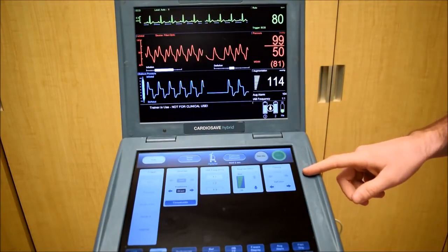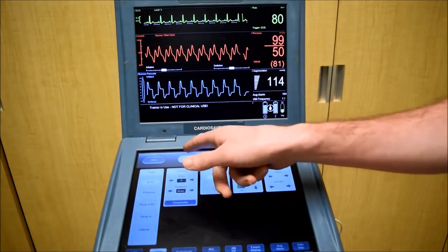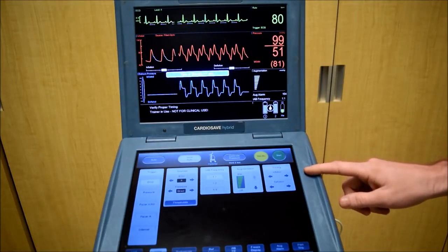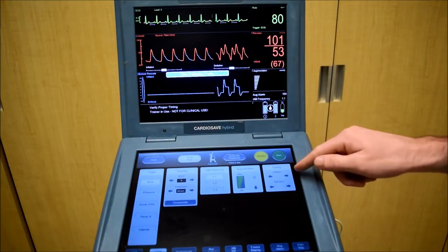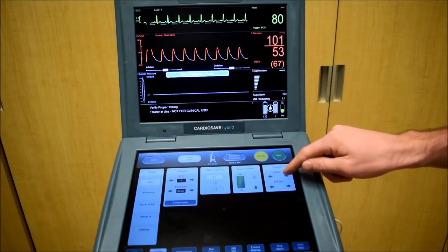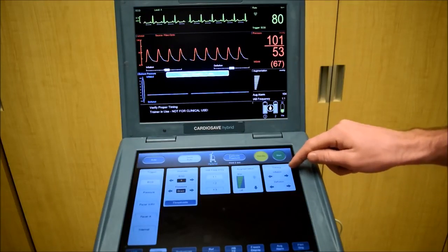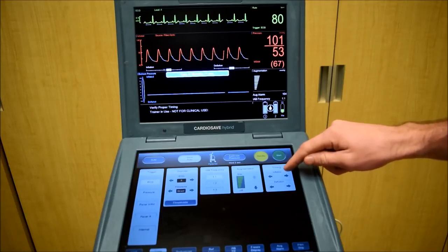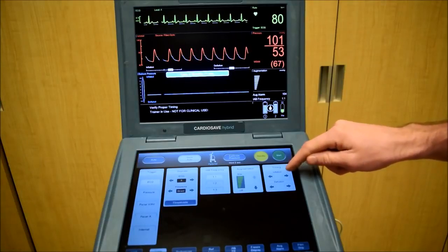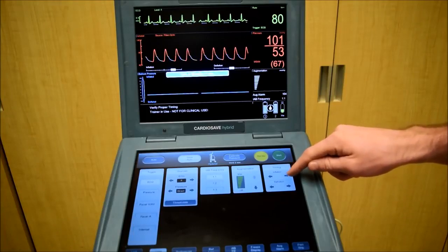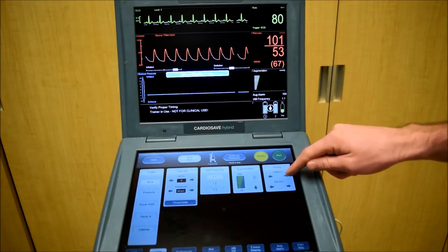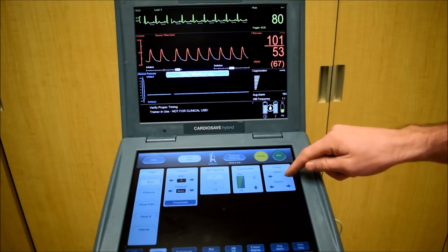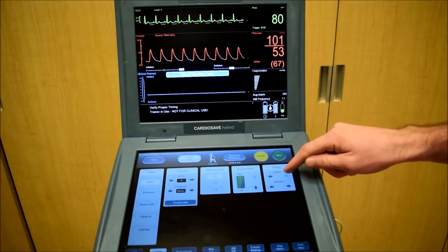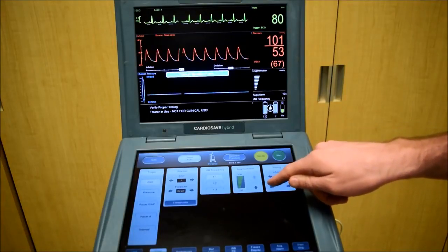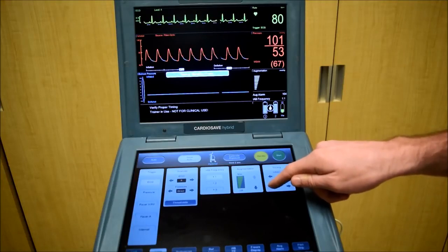Before I adjust the timing, I'm going to put the balloon in semi-auto mode so we can adjust inflation. Now again, the safest place is late inflation, so I'm going to adjust my inflation to be later, and early deflation. You'll notice below the pressure waveform, the inflation and deflation toggles are moving. So now deflation is going earlier.